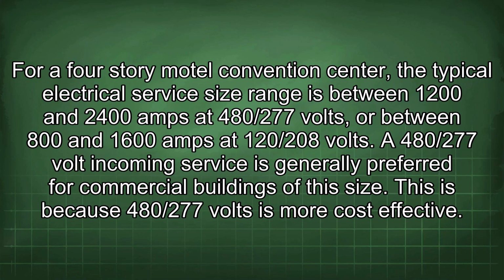For a 4-story motel convention center, the typical electrical service size ranges between 1200 and 2400 amps at 480/277 volts, or between 800 and 1600 amps at 120/208 volts. A 480/277 volt incoming service is generally preferred for commercial buildings of this size.